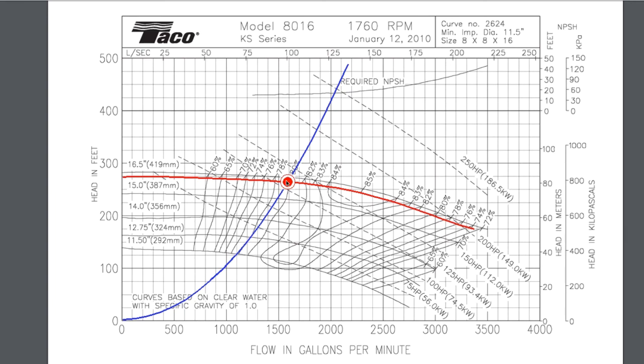What else can we find on this graph? The operating point is sitting just below — or right on — the 80 percent isoefficiency line. If we pumped a little more flow through, we could move up into a region of 82, 83, or even 84 percent efficiency. We could have higher efficiency if we matched the curve better and operated at the pump's maximum efficiency point. But 80 percent is still pretty good.